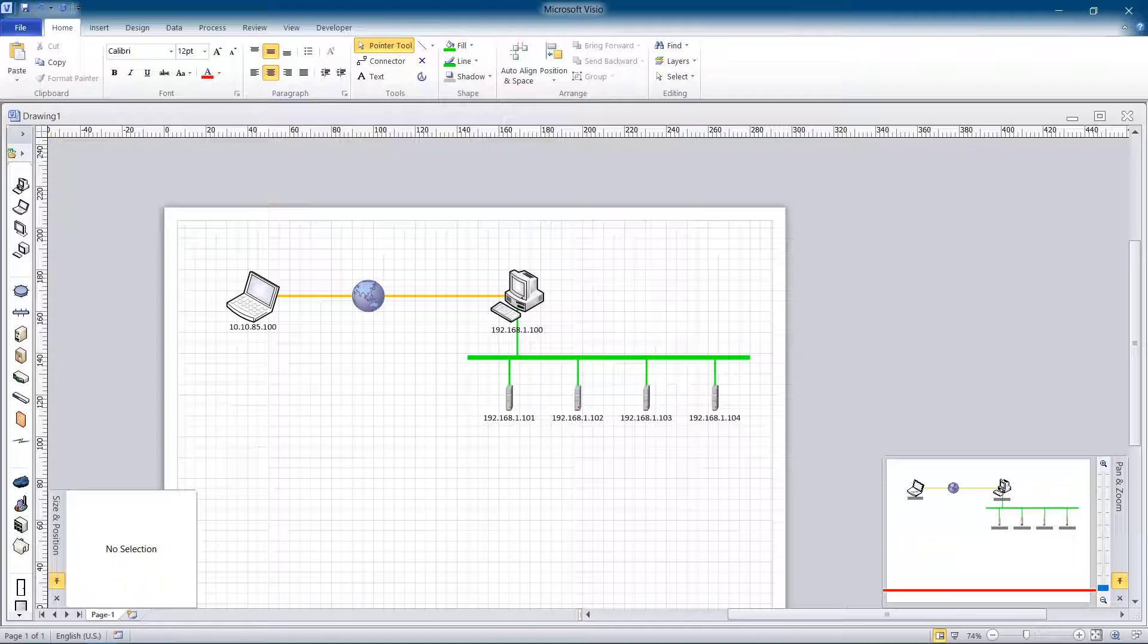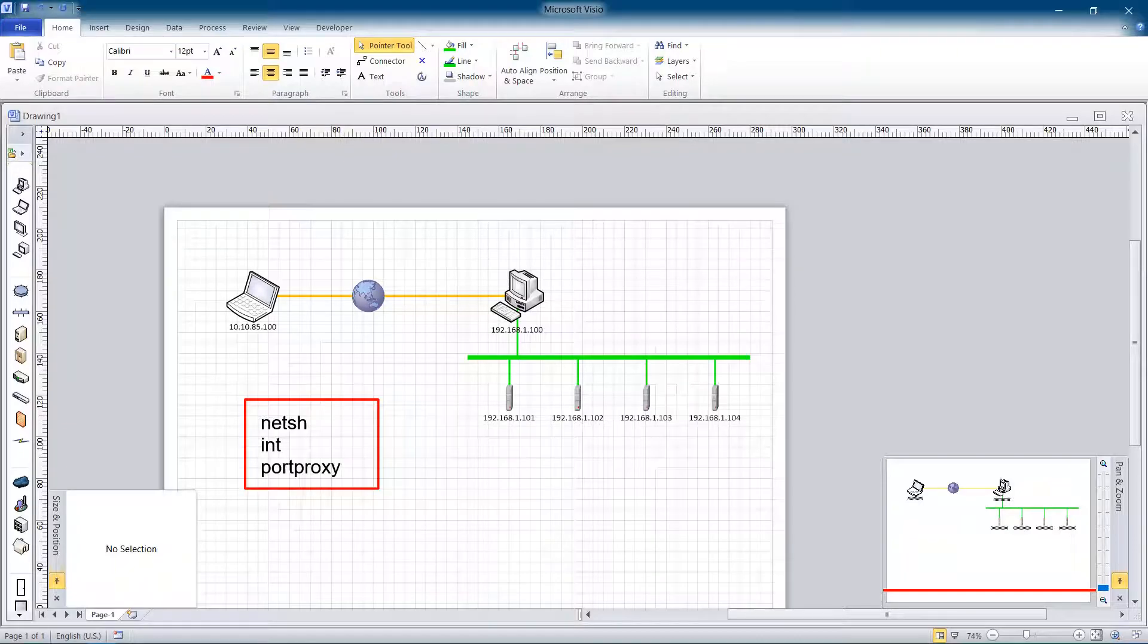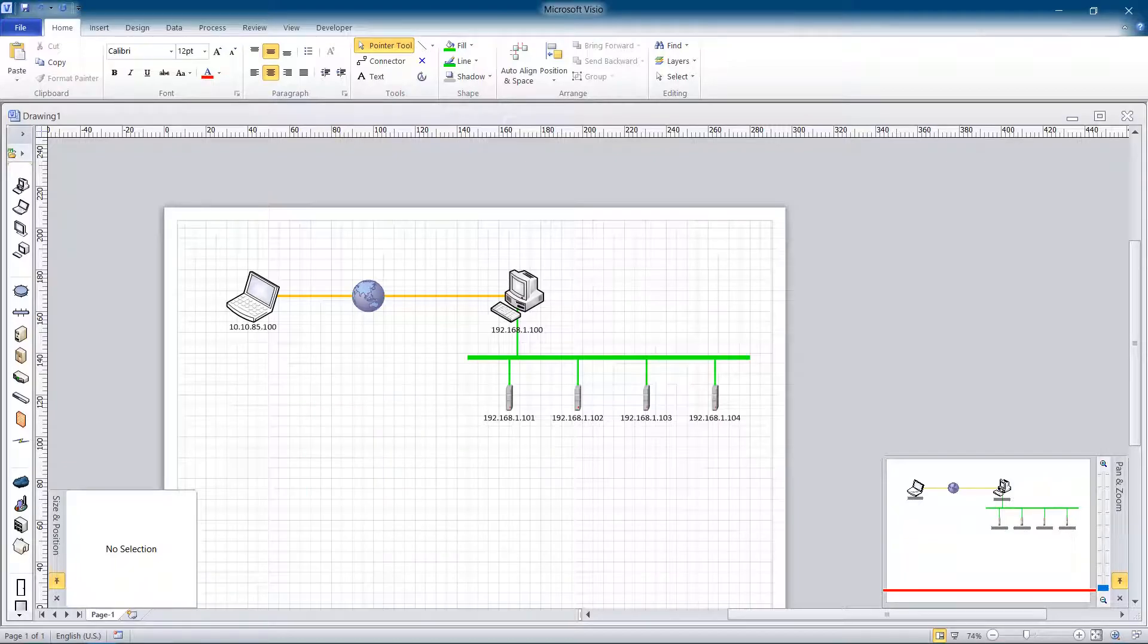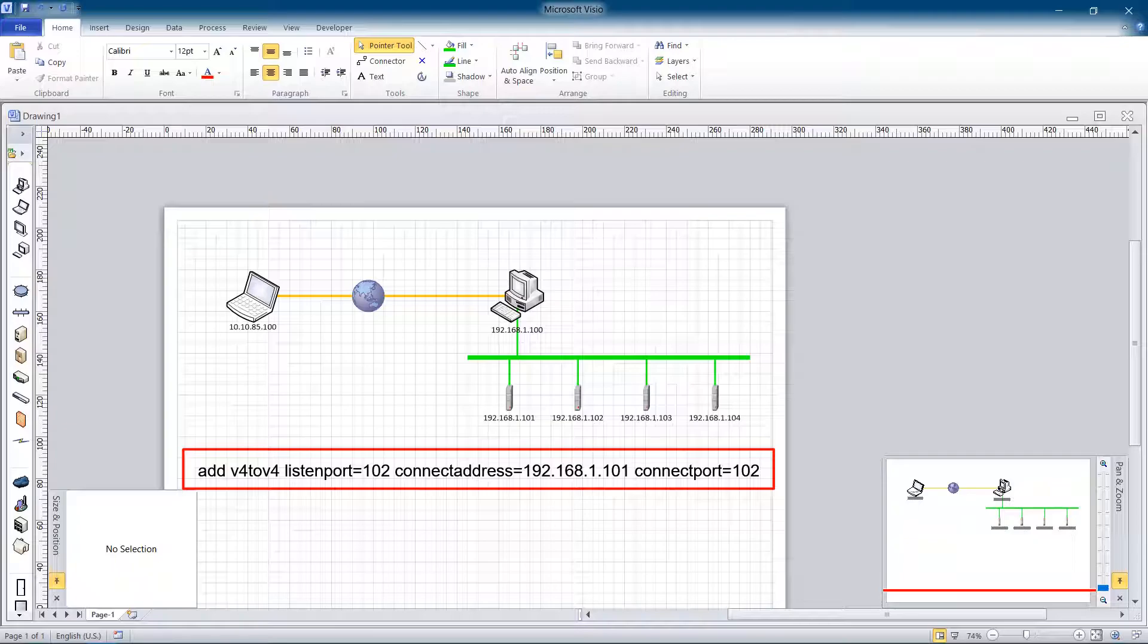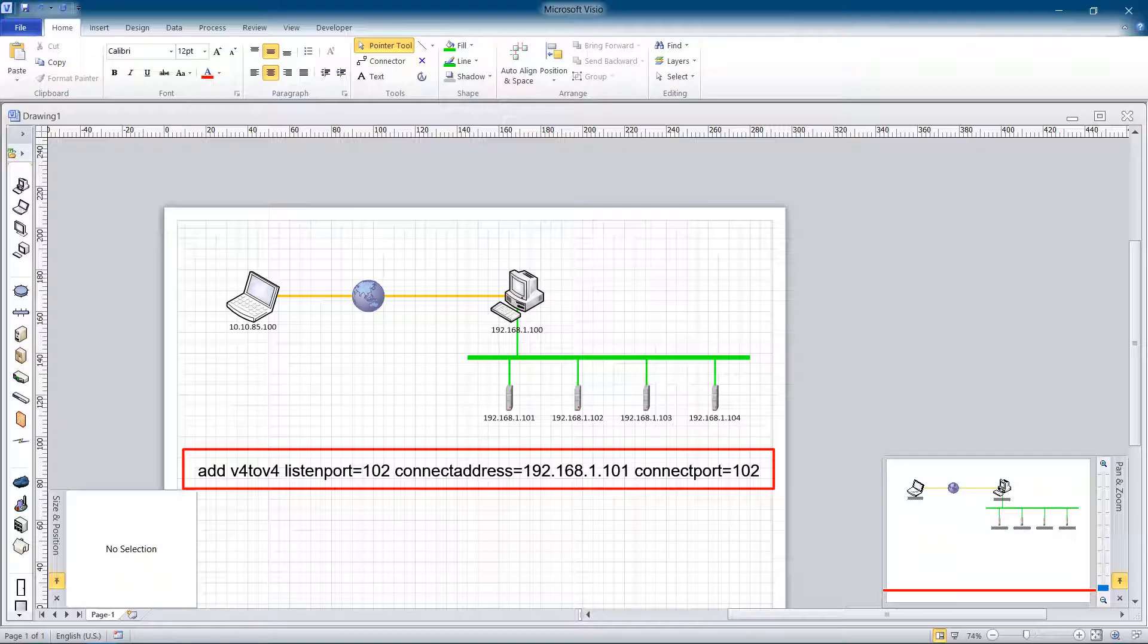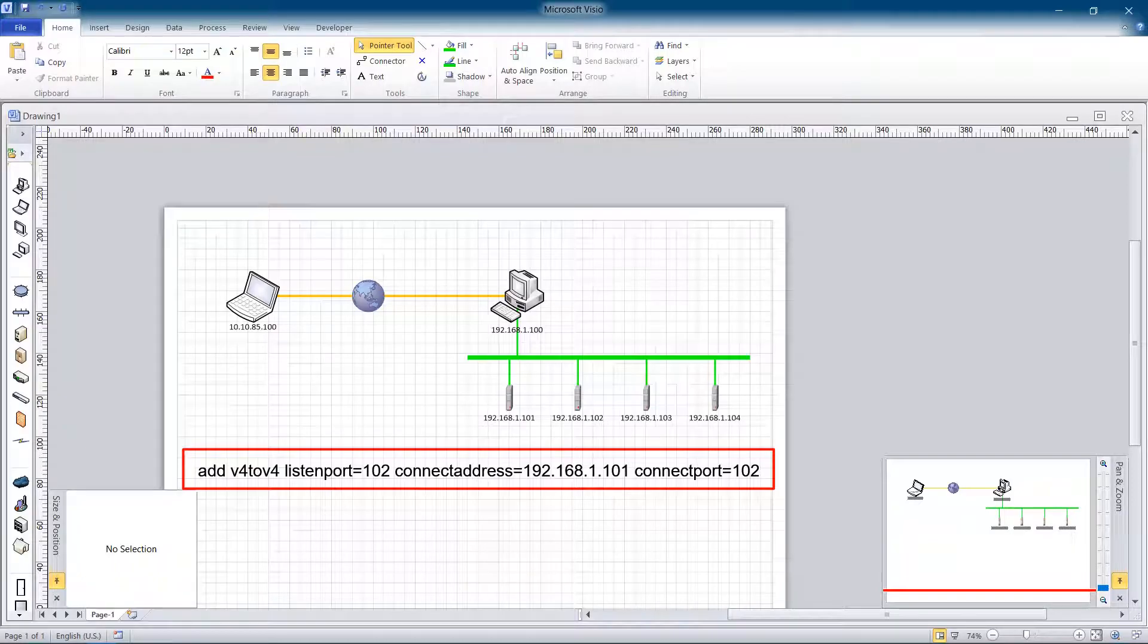Method number one. Open the Windows command prompt with elevated rights on the plant PC. Type in the following commands. Listen port and connect port are the ports that you are going to connect to and listen to. For Siemens PLCs port number is 102. You need to check your PLC to find out what port it uses.